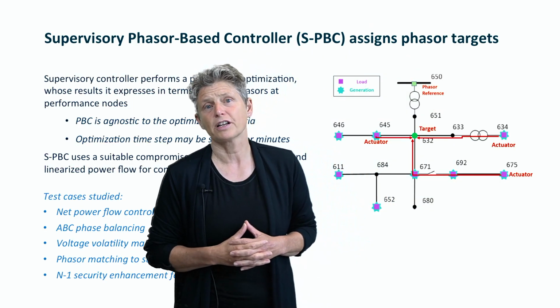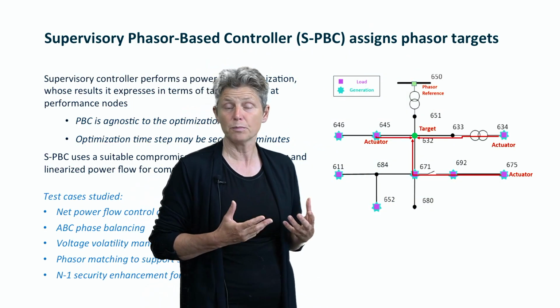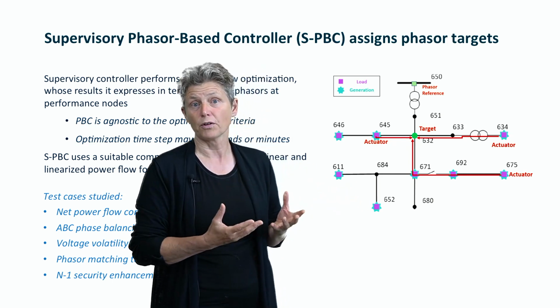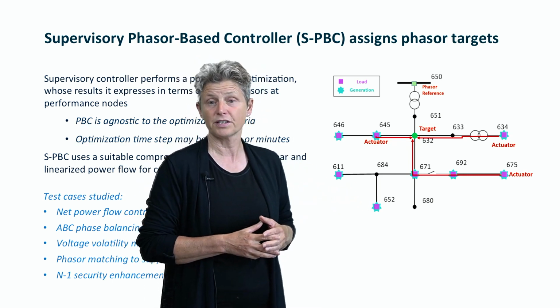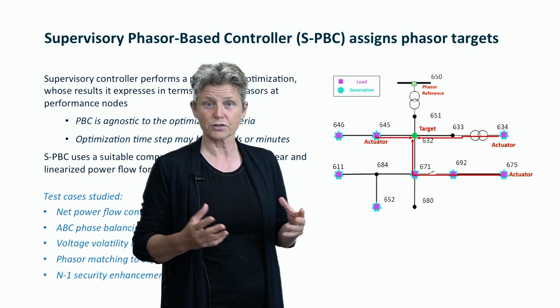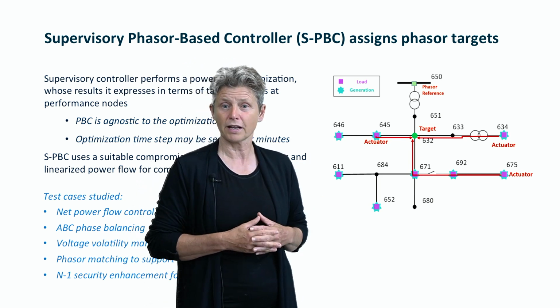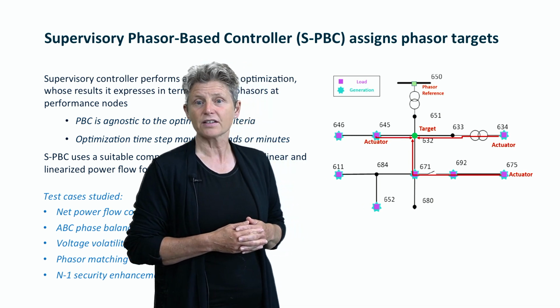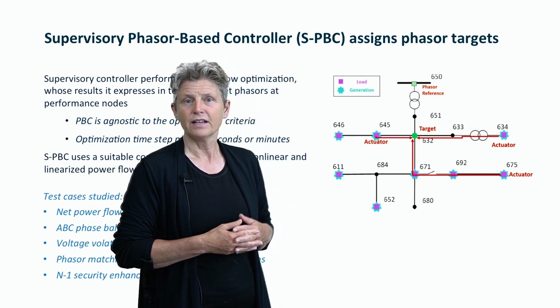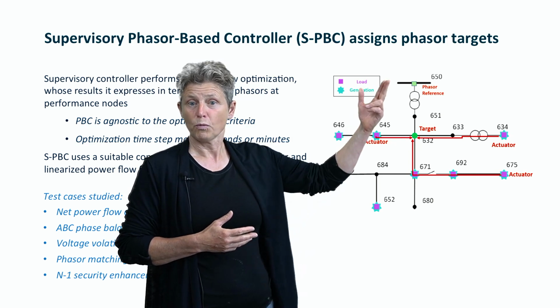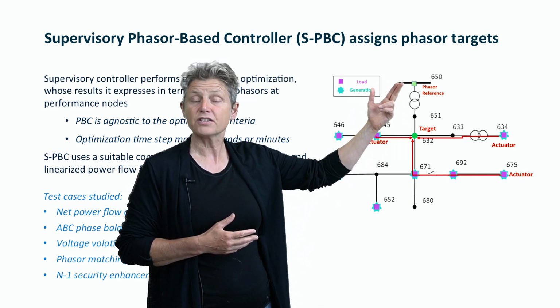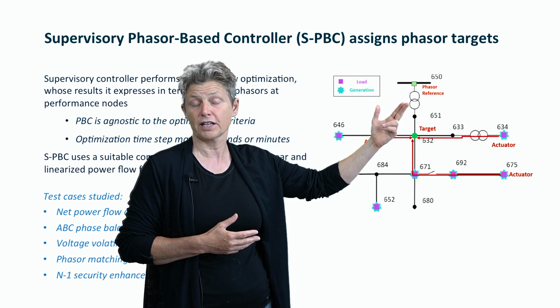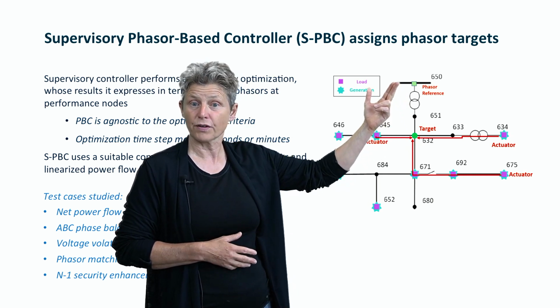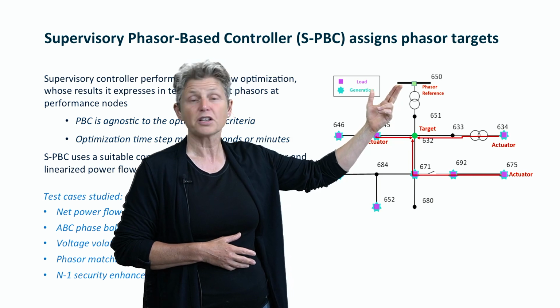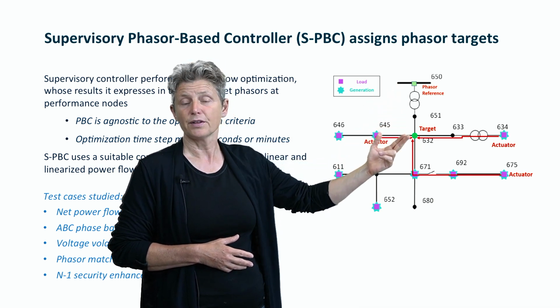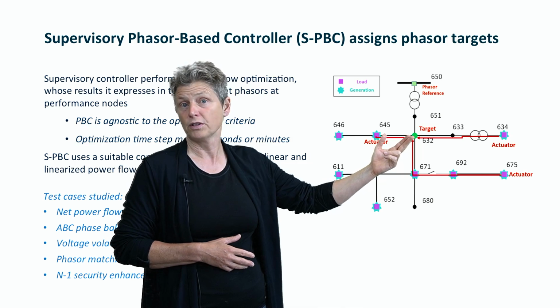In our project we did a lot of simulation, starting with small distribution circuits like this IEEE 13-node feeder. That's very well understood and straightforward, so we could play with it. In this case we had a control objective to hold constant the power flow across the transformer, meaning hold constant the phasor difference between substation bus 650 and this bus, node 632.